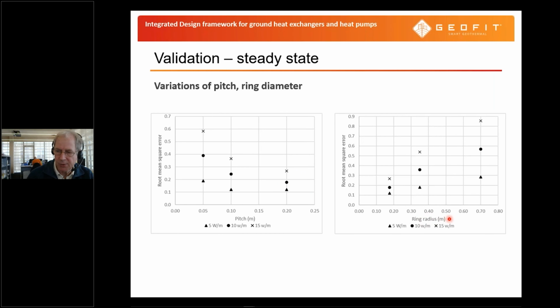We can also look at the radius of the ring itself, a large Earth basket or a small Earth basket, between, let's say, slightly less than 20 centimeters. That would be a spiral, for instance, in an energy pile, and on the other hand, a radius of 0.7 meters, so a diameter of about 1.4 meters, which would be an Earth basket type like we've installed in the demo site. And again, you see that the root mean square error has a relation with the heat injection rate and also with the radius, but still the overall errors remain pretty small in the steady state analysis. The maximum one is slightly higher than 0.8 Kelvin.